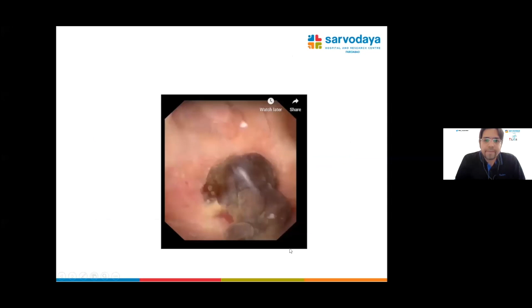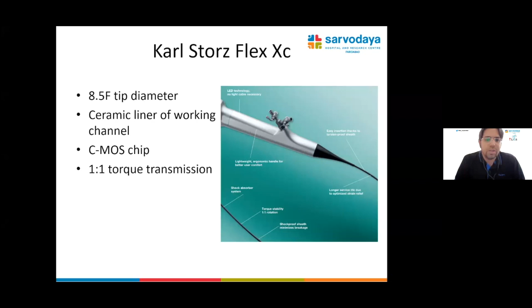So Karl Storz Flex XC, I believe, is the most preferred digital scope, and for me personally, this is a standard that I view any digital scope against, when I have to compare the image and the maneuverability. Karl Storz Flex XC has an 8.5 French tip diameter with a ceramic liner of the working channel. Again, this prevents damage while we are using the laser fiber very close to the scope. It has a CMOS chip on tip with a 1:1 torque transmission.